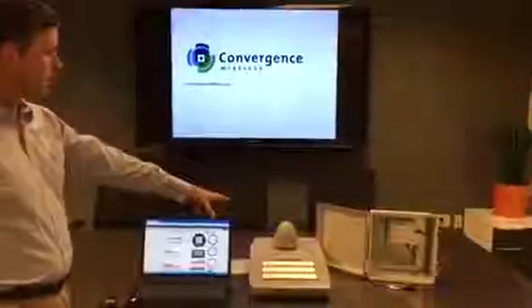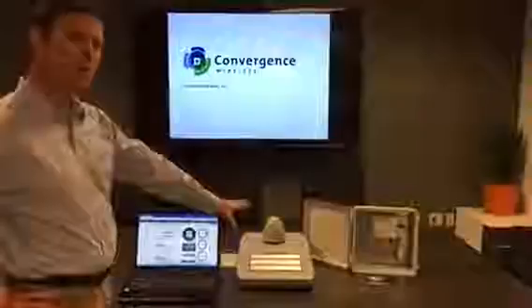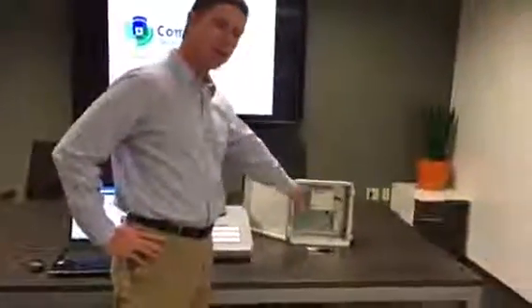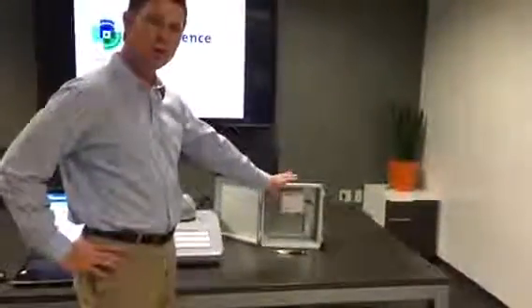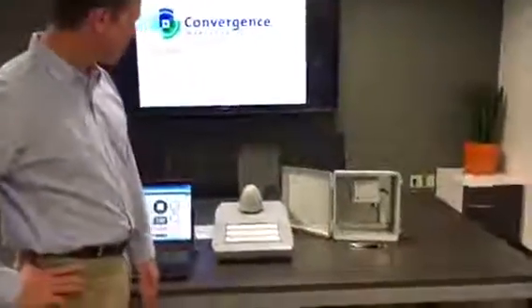We've got a streetlight from one of our partners, Polybright International, which is their Borealis line of LED streetlights. We've got our wireless manager here in the enclosure, which is a 12 by 12 enclosure. Because we're powering this off of 110 volt AC, we've got just a standard little DC power supply in there. The reason there's so much space in this enclosure is so that we can handle whatever voltage input you need. If you have 480 volts, 277, or 230 volts, we can accommodate that with the power supply underneath our wireless manager that you see inside there.